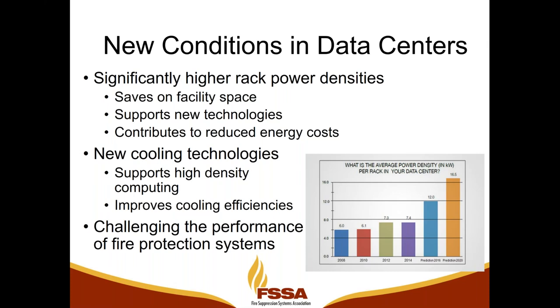And so what's changing there is the amount of power that a data center consumes is going up. And we see that in higher rack densities of power. So a rack is a large cabinet that contains many computers. And as we pack more and more computing power into a rack, the amount of power per rack has been going up for several years. And now we're seeing some very high consumptions. On average now, we're seeing consumptions of around 14 kW per rack, and a high-end rack is up to 30 kilowatts of power per rack. So high densities, whereas a few years ago, a 6 kilowatt rack was what we were used to seeing in data centers. To cool all that power generates heat.